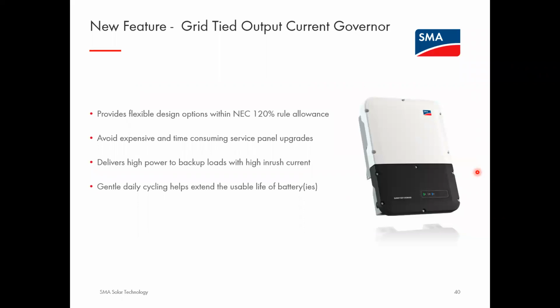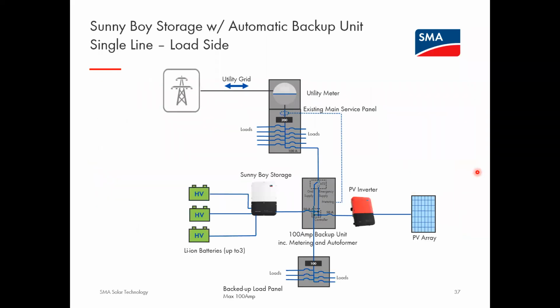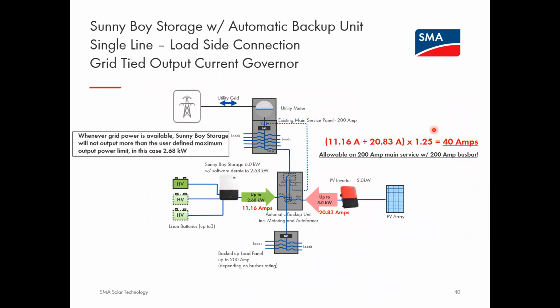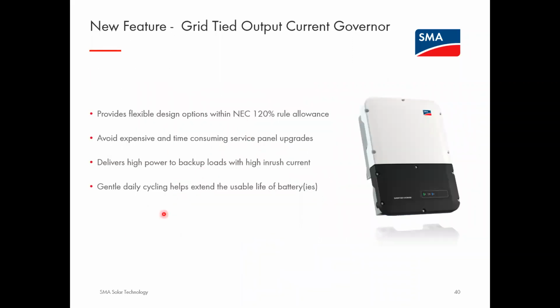There is a new feature, which you're some of the very first to learn about, called the grid-tied output current governor. I'll explain this briefly. It's a fairly complex concept, but at a high level, this is a workaround if you are connecting on the load side, like in this example of the main service panel. You are subject to the 120% rule, and that can sometimes be challenging with multiple inverters while still staying within the limits allowed under the NEC. So what we've developed is this feature which allows you to circumvent some of the rules in the NEC 120% rule, without compromising on the amount of backup power that's available during a grid outage.